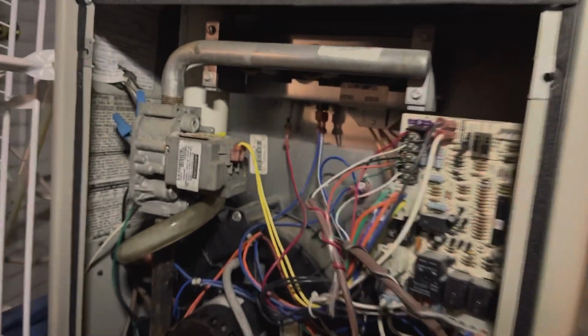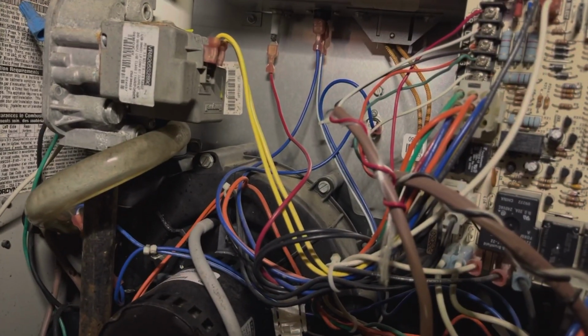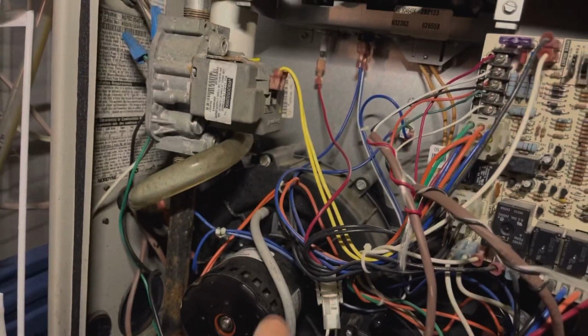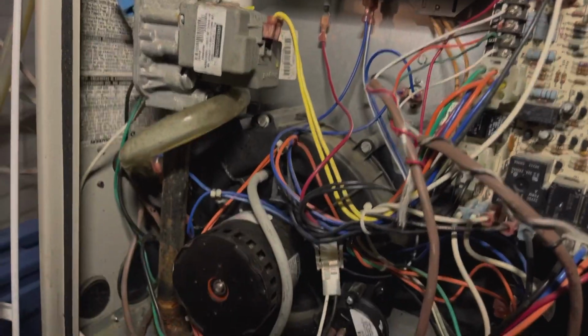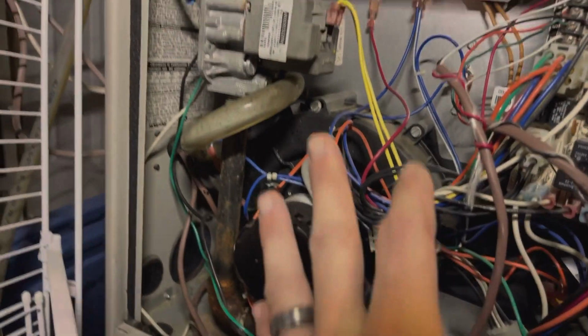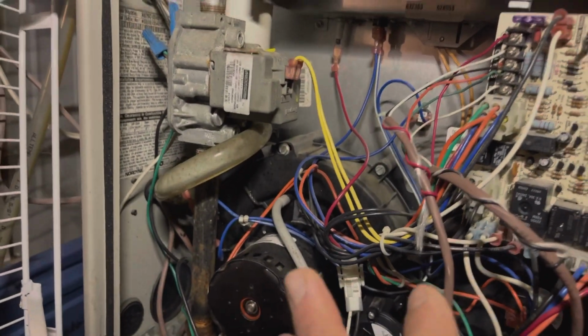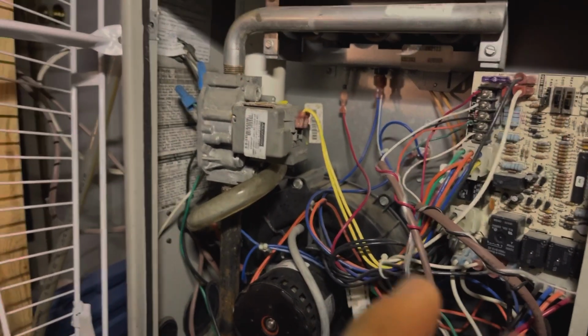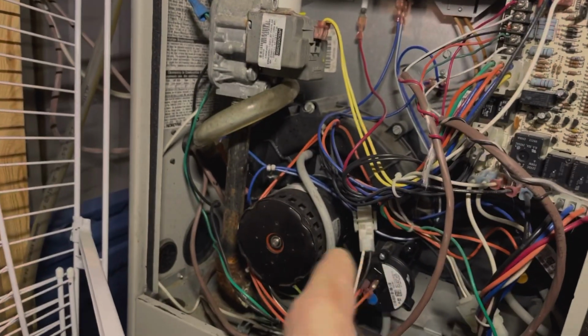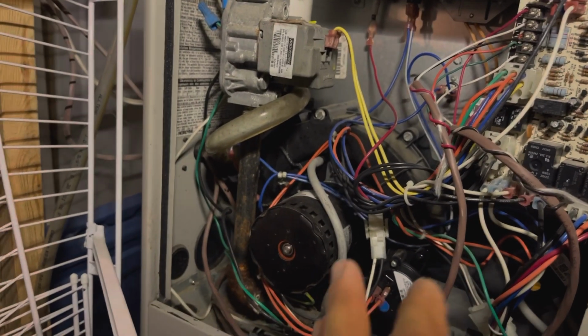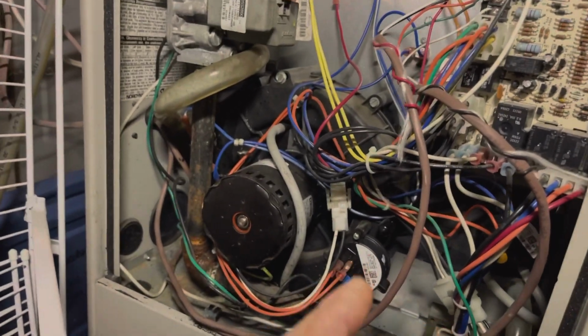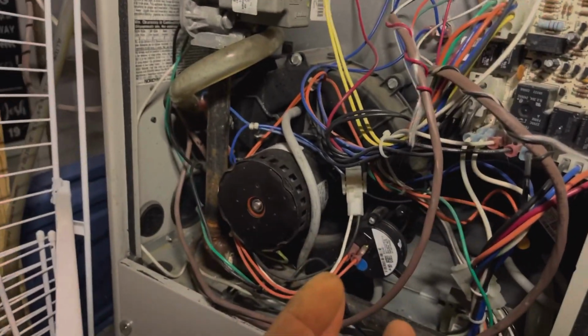So then a lot of your other common problems, you can see them all basically right here. These are most of your parts, and it's best to understand the sequence of operation of how the furnace starts up. It's got all of its safety switches, and if any of the safety switches go bad, it won't start up, or if they're just triggered because something's wrong with the furnace. So we'll get into that in a second.